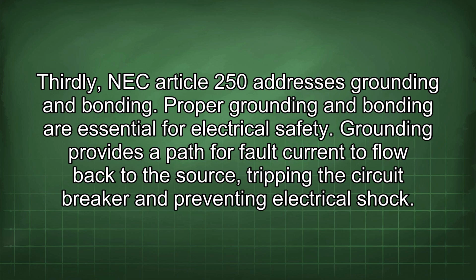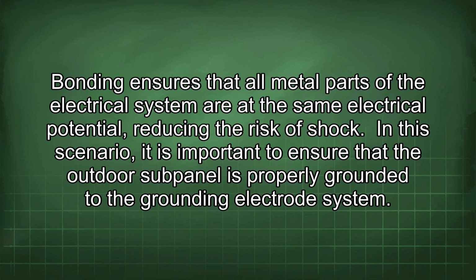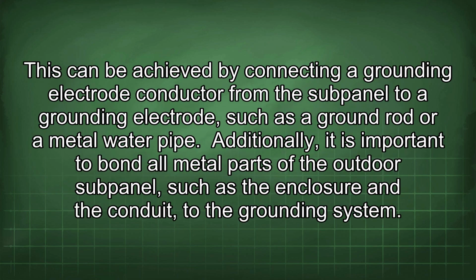Proper grounding and bonding are essential for electrical safety. Grounding provides a path for fault current to flow back to the source, tripping the circuit breaker and preventing electrical shock. Bonding ensures that all metal parts of the electrical system are at the same electrical potential, reducing the risk of shock. In this scenario, it is important to ensure that the outdoor subpanel is properly grounded to the grounding electrode system. This can be achieved by connecting a grounding electrode conductor from the subpanel to a grounding electrode, such as a ground rod or a metal water pipe.